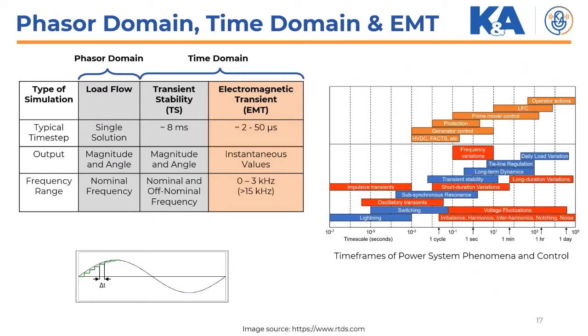In this slide, we see the time required for these types of studies. For the phasor domain, it is not a time base. It just gives you one snapshot of the system. The time domain has two types of studies: transient stability, which is in the order of milliseconds, and electromagnetic transient, which is in the order of microseconds. It's for simulating fast phenomena like switching in an inverter, and to see how that affects the system. And on the chart on the far right, you see different phenomena, their time scale and the order of the time.